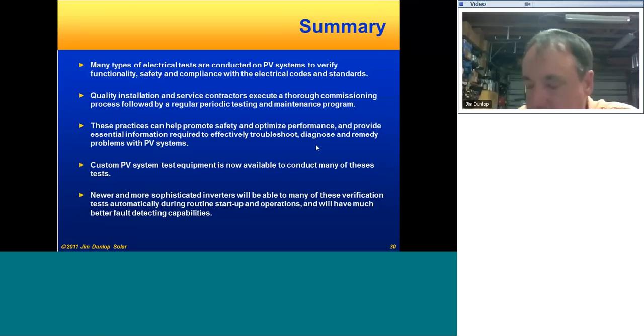Still, there's that issue. If you have a ground fault in a fairly large array, if you don't have string level monitoring, it's going to be very, very difficult to find it without being able to go through and do insulation resistance testing. It's not going to be something you visually can see. It'll be almost impossible to determine which circuit it is without doing those kinds of tests.